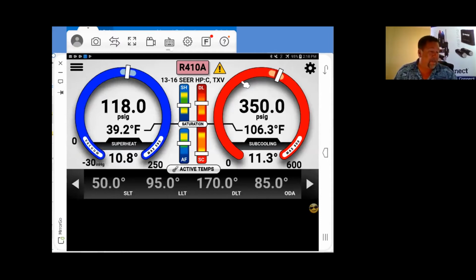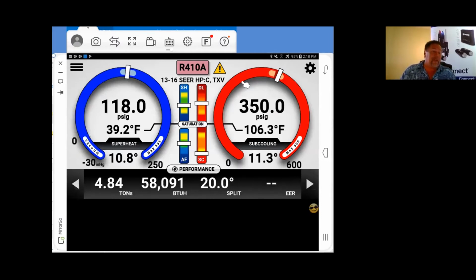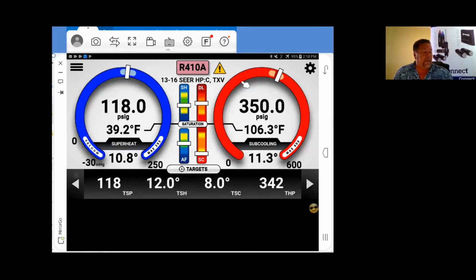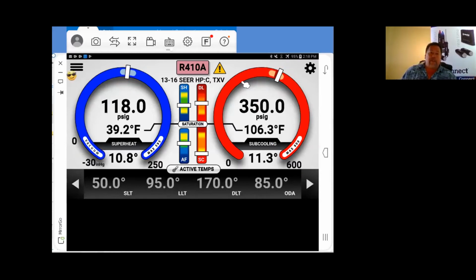I'm sorry, but out of trying to take this out of demo information, it wouldn't let me do it. I apologize. But taking that out, taking the air side out, it won't establish your targets because you need both supply and return air temperatures to establish your targets on your pressures. You need both of those. But as far as your superheat and subcooling targets, those will establish. You'll put those in. If it is a fixed orifice, straight cool system, it'll range your superheat, and it'll go ahead and calculate it up for you.